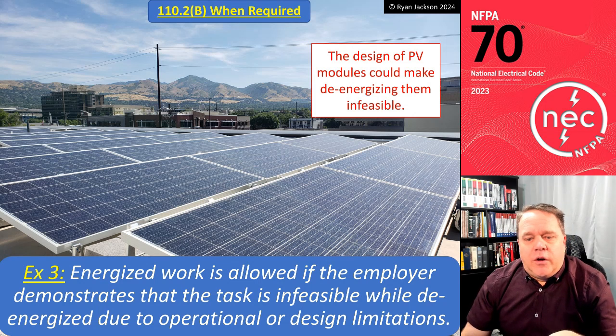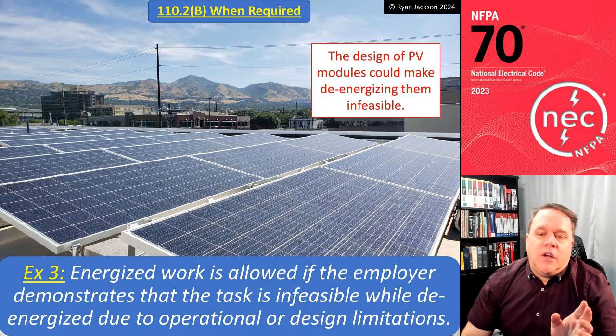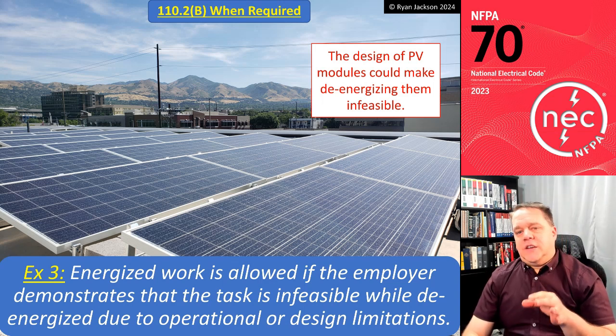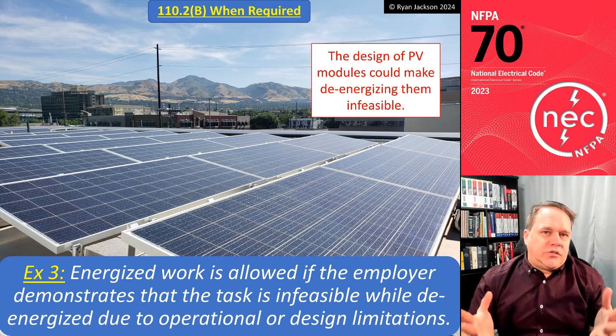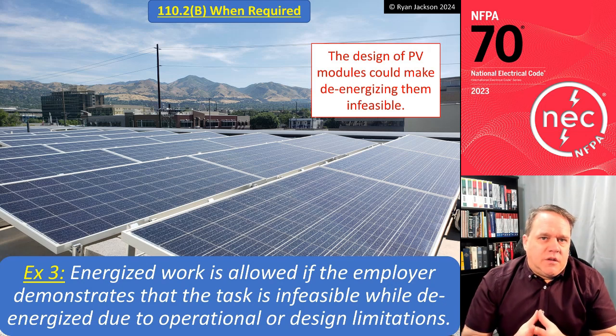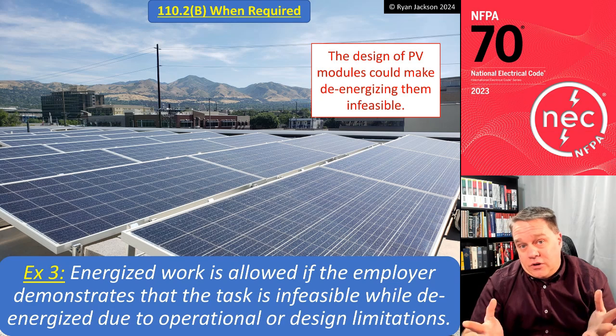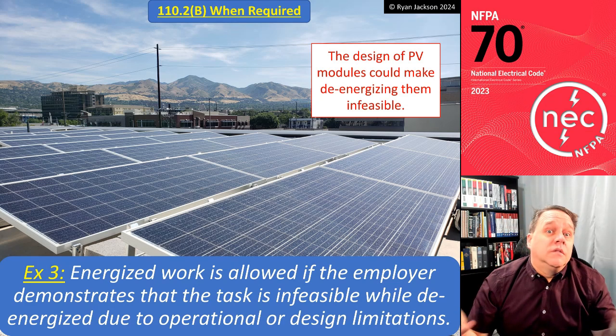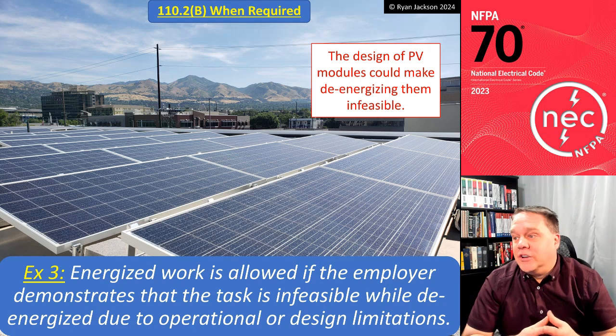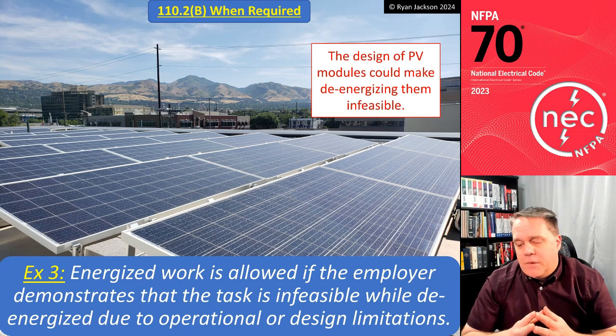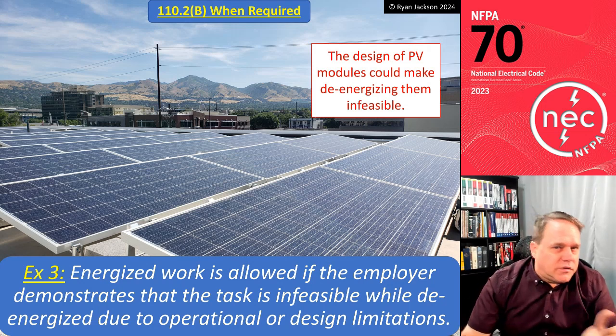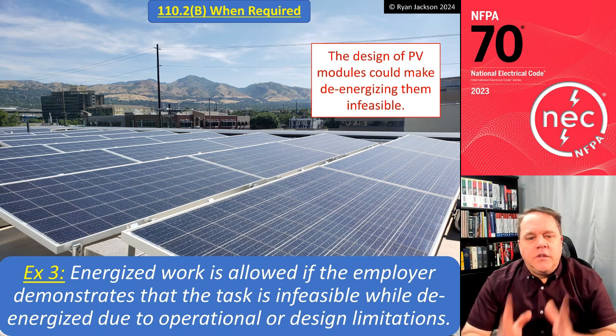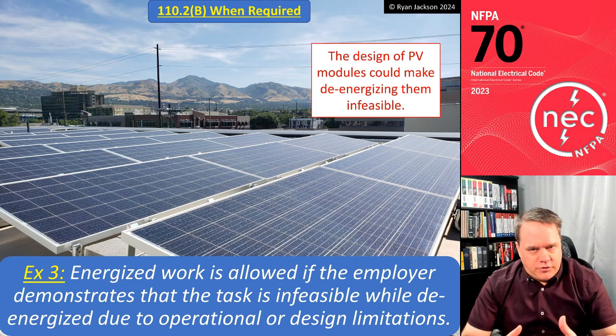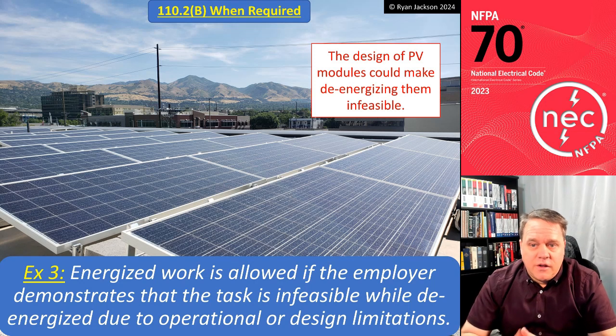Energized work is allowed if the employer demonstrates that the task is not feasible while de-energized due to operational or design limitations. I like to use solar PV as an example for this because it's pretty difficult to shut off solar, right? Unless you're shutting off the sun, you usually can't really shut off solar. You can shade the module, but that's not always feasible, depending on what we're doing. So this could be an example of where shutting it off just isn't feasible due to operational or design limitations.